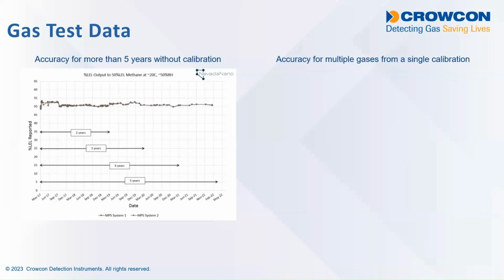In portable applications, it can also depend on, if you use your portable instrument on site during the day and the site is nice and clean, that's great. But then if you put your portable instrument in the back of your van where you've got some of that polishing compound, your portable instrument can be poisoned overnight just by laying in the van with some silicone. So it completely depends on the application, and the key point is you have to keep gas testing your pellistor to be sure it works. That's absolutely paramount. With the MPS sensor, it can't be poisoned, so that need to keep testing it is greatly reduced.